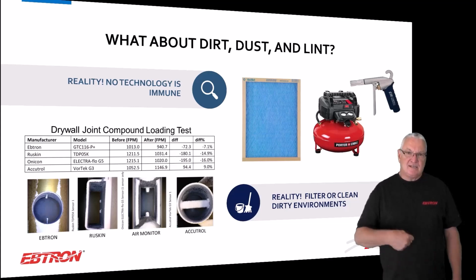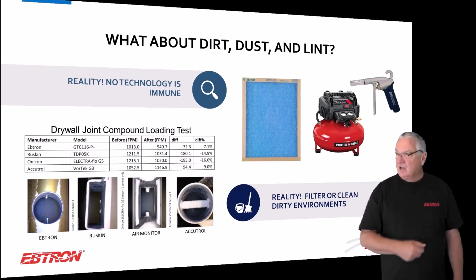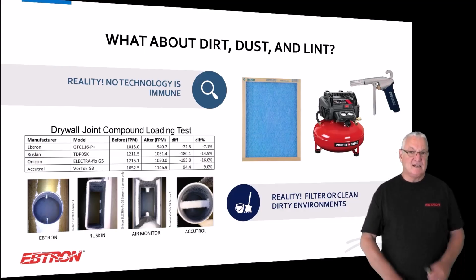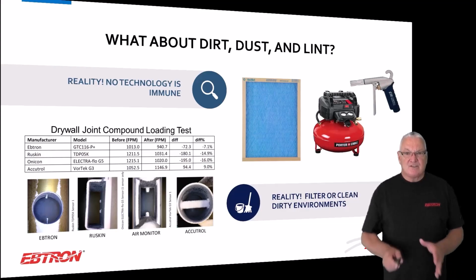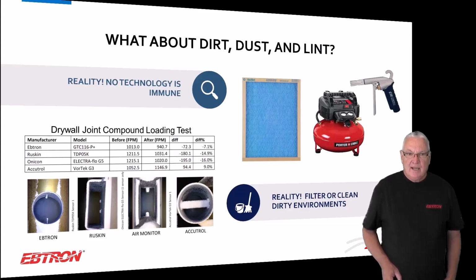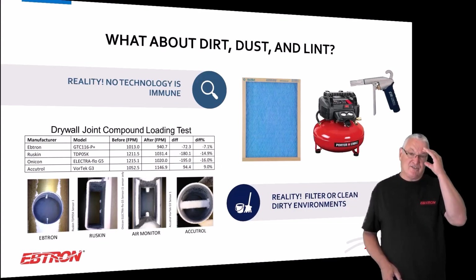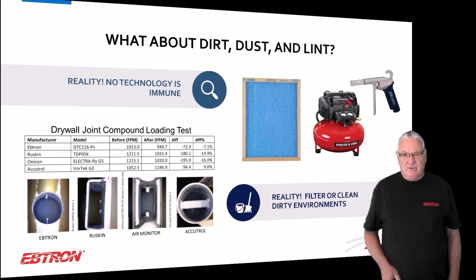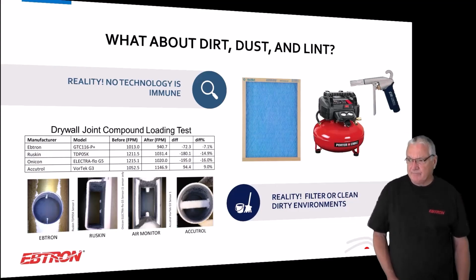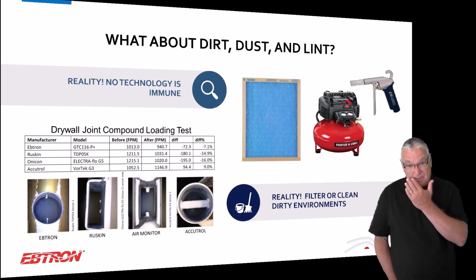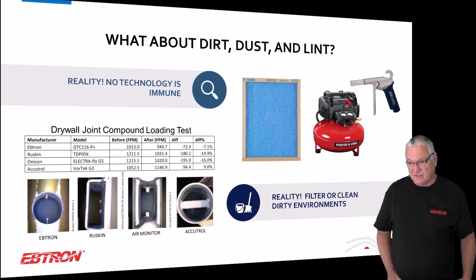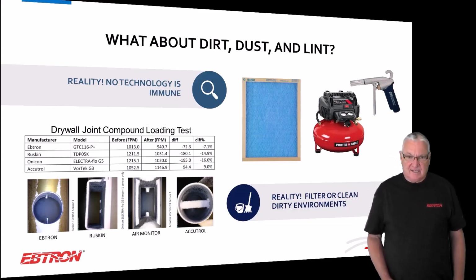And I've decided at 62, going on 63 years old, I'm tired of not saying this. This is going to be my position from here on out. Okay? Because that's what we need to do. And I'm going to keep pushing it, and what I've seen, and I'm not necessarily suggesting that you only do this, the cheap blue filter in the return grill, because there are advantages of pre-filtering a little more of that material out and saving some of your HEPAs and things like that, even though you do have other pre-filters. Not having to do duct cleaning and things like that is a great deal.